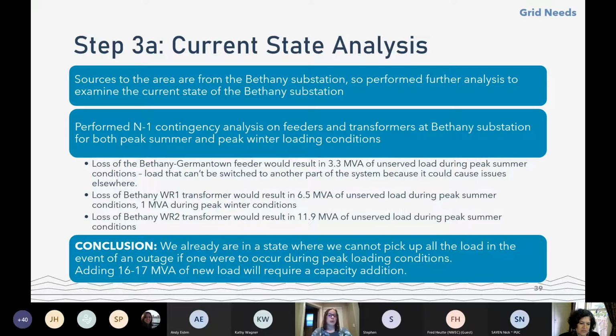Like your June 28th, 2021 type of summer, and your February ice storm type of winter loading conditions - the top times where we have the most demand on our system. We apply that and run multiple different scenarios individually. For example, the first bullet here, the Bethany Germantown feeder - we saw that if we lost that feeder, before adding the new load to the system, we already had some contingency issues. So on our hottest summer day, if we lost that feeder, we would have over 3 MVA of load we couldn't serve, because trying to switch it to other parts of the system would cause issues elsewhere, like low voltage issues for customers being served from a substation that's too far away.